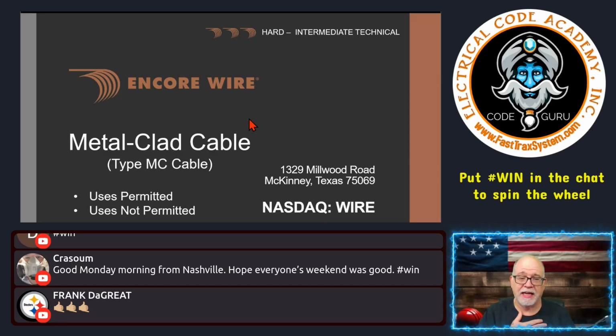I can't govern that, and the NEC is not going to govern that. The only thing the NEC is going to say is, if you do a new service, and it's not for emergency situations where you're just replacing from the service point down because of a storm or damage or something like that, then that wouldn't kick in any of the requirements. But if it is literally a service change, then your jurisdiction may kick in the requirements. So you might have to put SPDs in, right? Surge protective devices per 230.67, I believe. Don't hold me to that, but I remember.